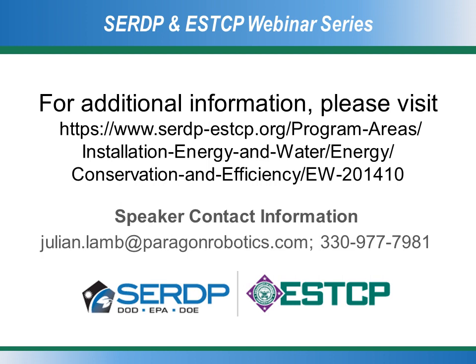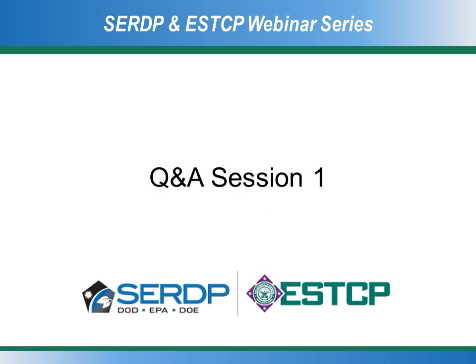Correct, yes. So as part of all of the standard M&V methodology, you look at a typical meteorological year. The data is pulled from the NOAA site to get on-site data, or we can utilize data streams from Paragon sensors or other sensors placed out there. So yes, that is fully factored into the simulation. And then when they're looking at the calculated savings, they typically scale those to a typical meteorological year as well. So climate is definitely taken into effect.